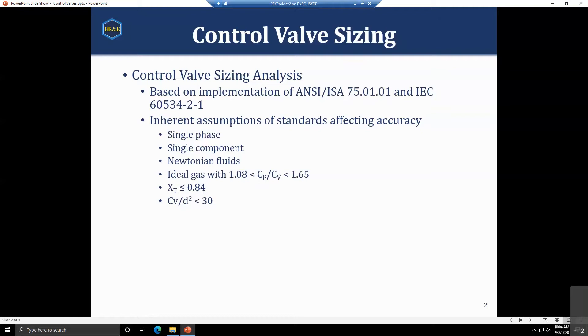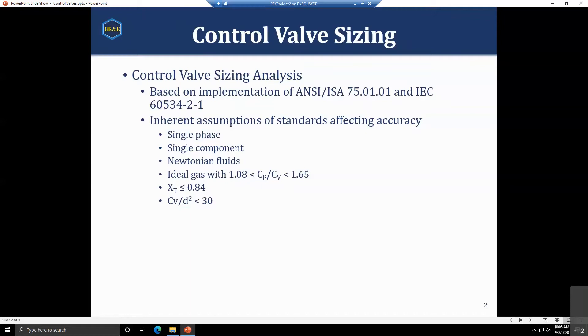The standards have inherent assumptions affecting accuracy. They're best used for single phase flow, single component, Newtonian fluids. The vapors should have ideal gas heat capacity ratios between 1.08 and 1.65, XT less than 0.84, and CV divided by valve size squared less than 30.